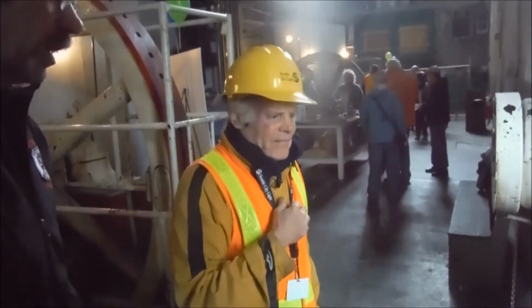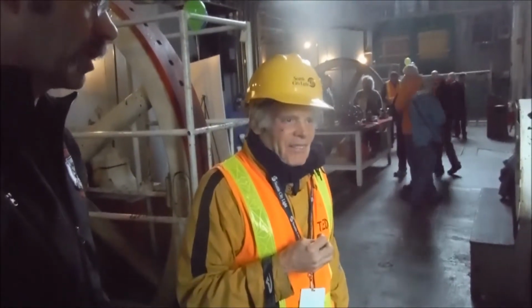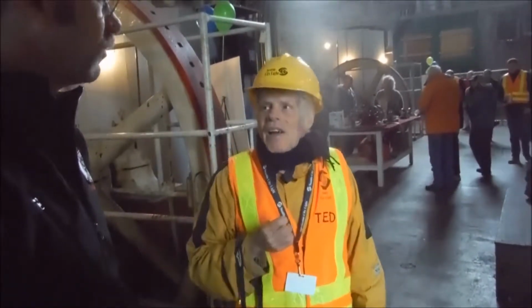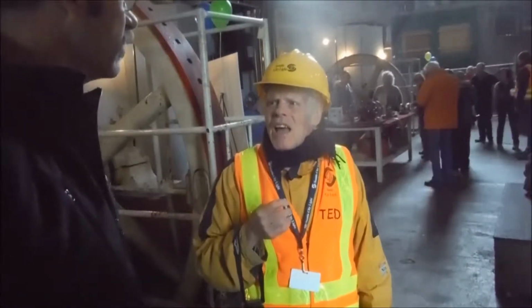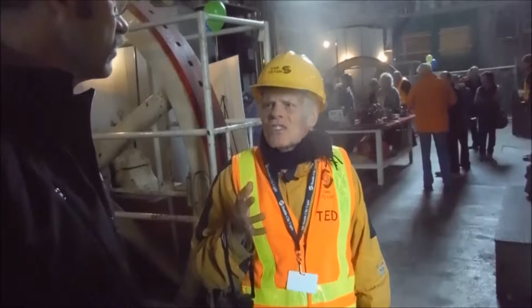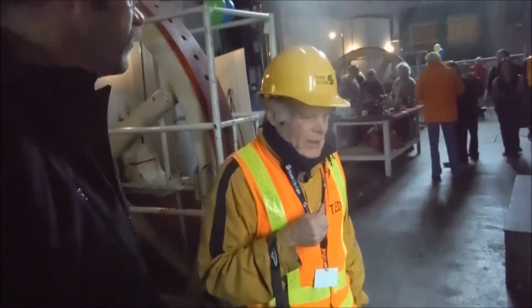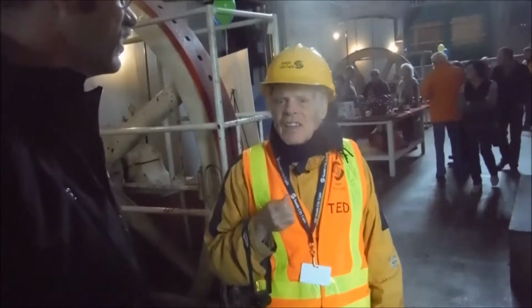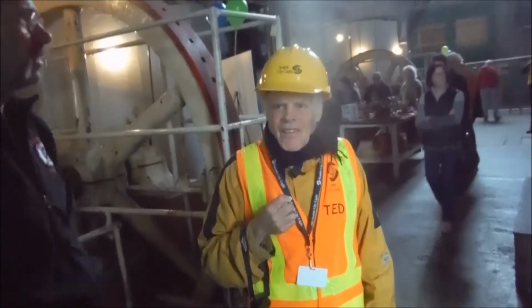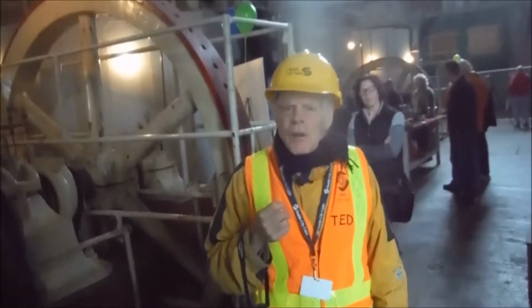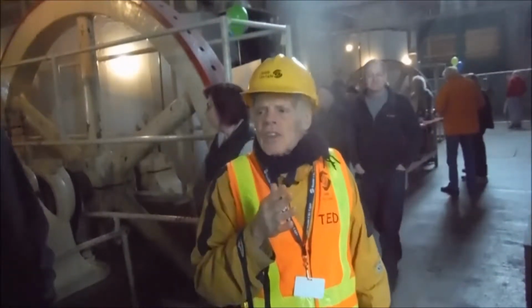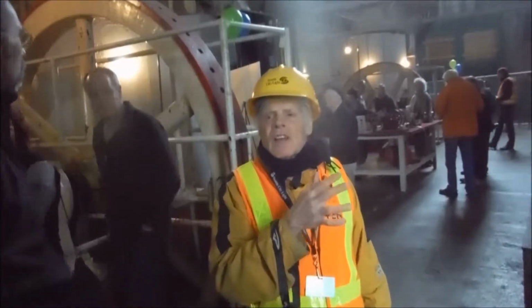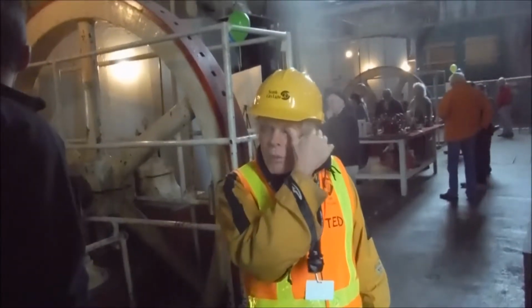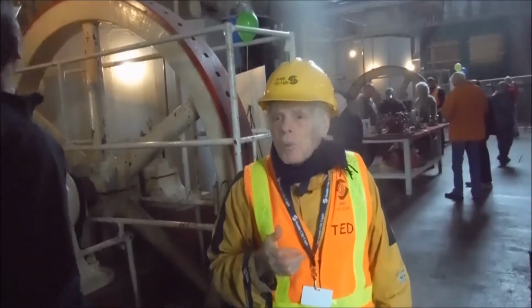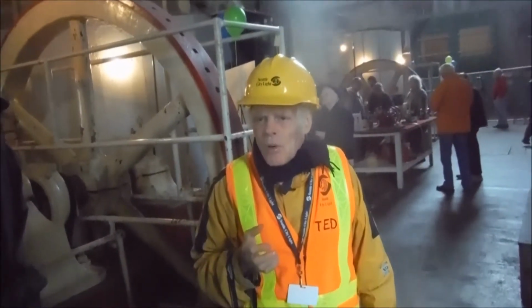Okay. Sort of like the procedure I had to use in the Navy to parallel 2 generators so they were working in phase before you brought a new generator online. Except this is DC, not AC. Yeah, DC. And on DC, you still have to have the voltages equal. Yeah, the voltage has to be equal. You usually have to have it in phase, but there is no phase on DC. Yep. Equal to within how close of a tolerance? It depends upon the machine, but if you have one machine overexcited, you're going to get a circulating current in the weaker one, and then you could possibly end up motoring it and causing damage. So. Okay.